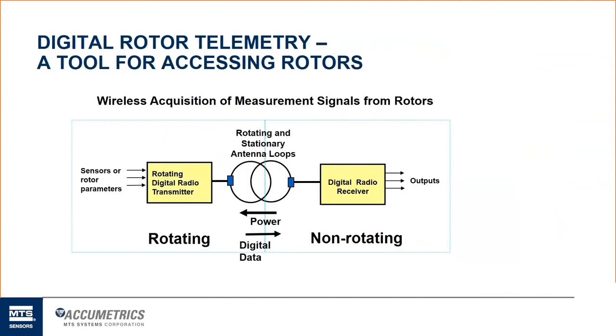So here's just a basic diagram of how it works. It's taking some type of sensor or rotor parameter, in this case, a field voltage and field resistance. It takes that information into our rotor mounted transmitter, which is an analog signal. We do some analog to digital conversion. We transmit that signal through essentially a loop of wire. There are two loops of wire, one on the rotating world, one on the stationary world, that forms that rotary transformer and creates that communication link between the rotating part and the stationary part.